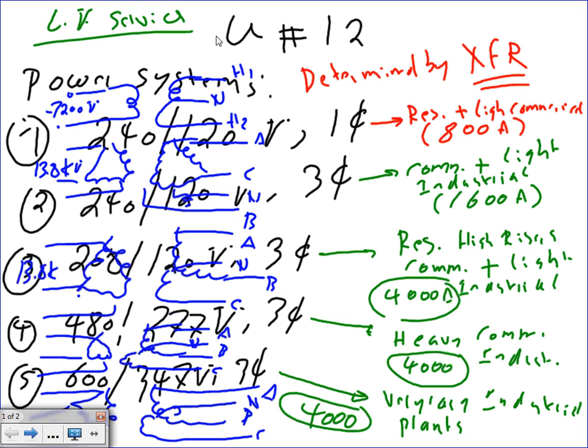Okay. So these are 5 types of transformers, guys, used in the industry. The first one, I know it's busy, I'm sorry. If you look at the blue, the blue is the first one. This is a single phase transformer, 7200 volt on the primary. On the secondary side is 240, 120, 2 hots. Very commonly used single phase residential, plus light commercial up to 800 amps. Don't hold me on the amps, please, but these are kind of plus or minus.